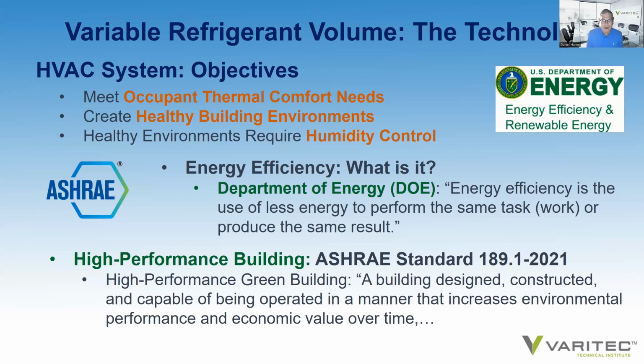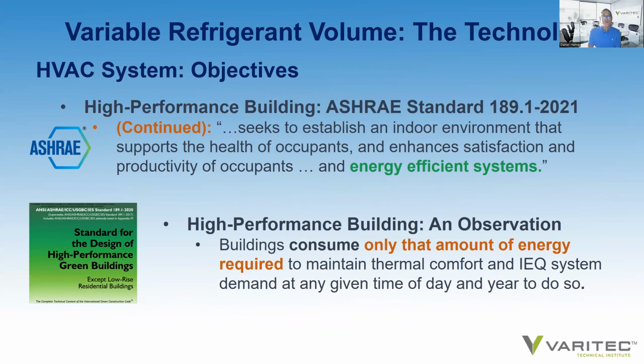ASHRAE's Standard 189.1 is their high-performance building design guideline, and it embraces the holistic approach of designing HVAC systems so that they are capable of being operated in a manner that increases environmental performance and economic value over time, and seeks to establish an indoor environment that supports the health of occupants and enhances satisfaction and productivity of occupants, and maintain energy efficient systems. So if you're looking at securing both objectives for a building of improving IEQ as well as system efficiency, ASHRAE Standard 189.1 would be a standard you would want to probably look at. So effectively, a high-performance building achieves the objectives of an HVAC system while only consuming that amount of energy necessary to meet that demand, to meet that load at any given time of day and at any given time of year.